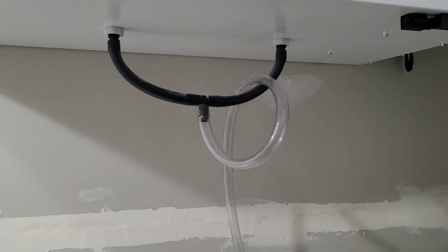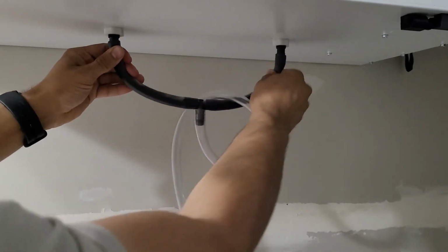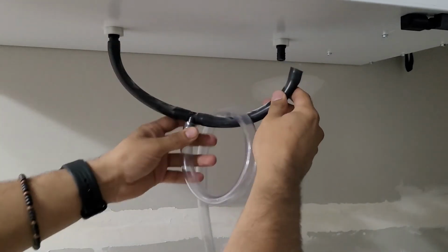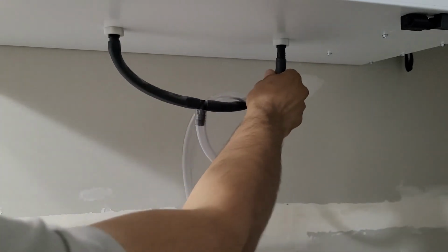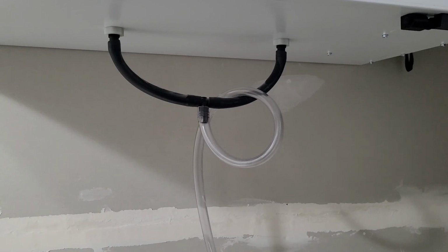So it's very simple. Just open your pipe. You can remove these parts very easily. You just have to shake it slowly and this will come off, and then you can clean it with hot water, or you can also use vinegar. So what you can do is remove this part, keep it in a 50% water, 50% vinegar solution overnight or for a few hours, and then you can properly rinse it and install it back. And you can do the same thing for your furnace condensate line.